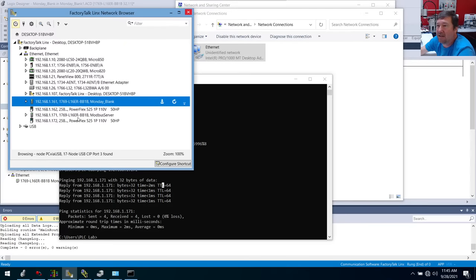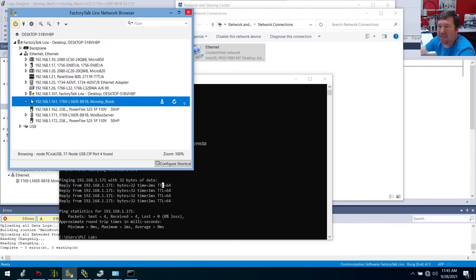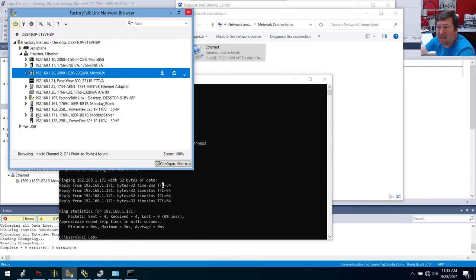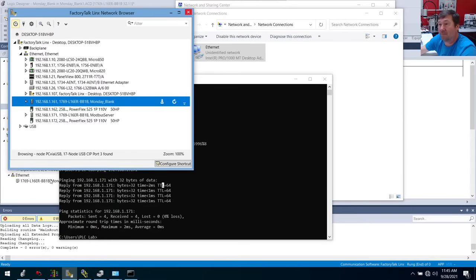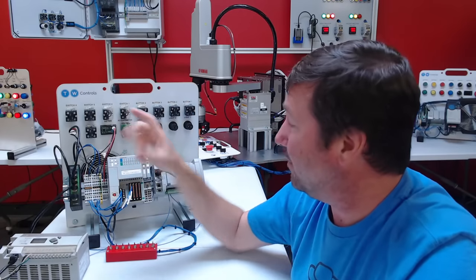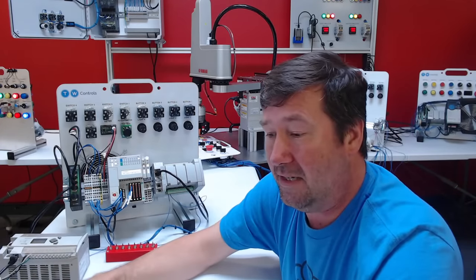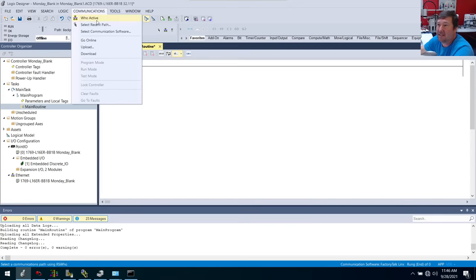Now we have multiple ones here, and here again is where I tell you all the time that you've got to make your PLCs memorable. The guy on the phone told us it was probably 171. But this PLC looks exactly the same as this PLC icon, and you notice we've got some other ones up here that look really similar. Was this the Modbus server, or was this Monday blank? We happen to know we were on it with the USB. If you recall, we plugged in the USB port, and the name that showed up under USB — that we ended up uploading our program with — is going to be the same name that it identifies as over Ethernet. So now we know that the one we want is this one right here.